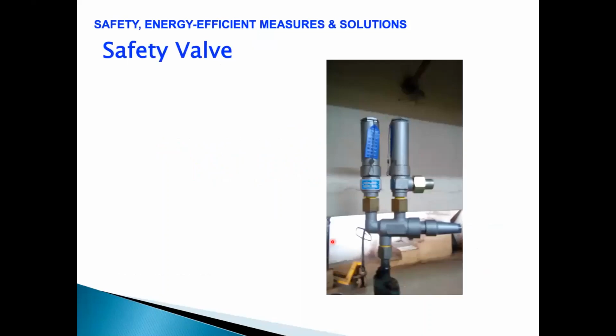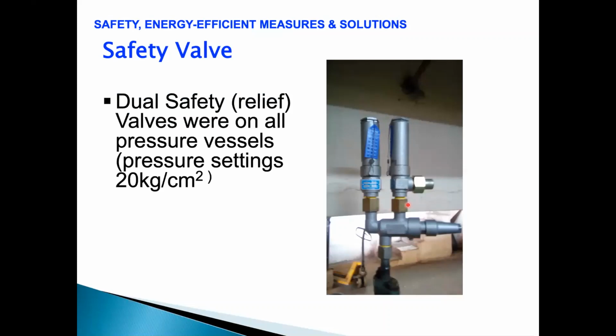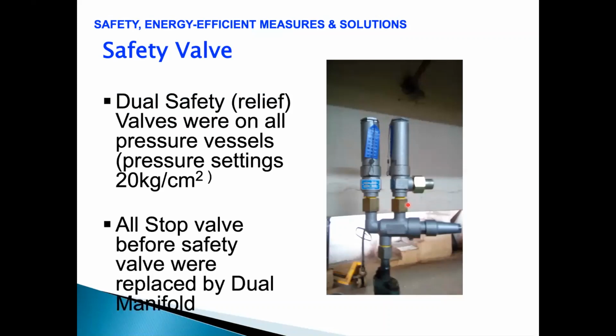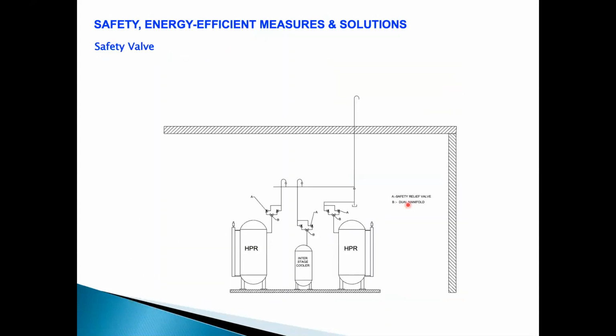So what we have done is we have decided to implement multiple solutions. First part was to implement a safety part. All the single safety valves were replaced with dual manifold safety valves. And as per the required pressure, all the stop valves before the safety valve were removed, because that way nobody can isolate those things. A safety relief system was provided, where all the outlets of the safety valves were connected to one common header and brought out around 20 feet above the factory terrace. So there was no human being exposed in case a safety valve pops up.